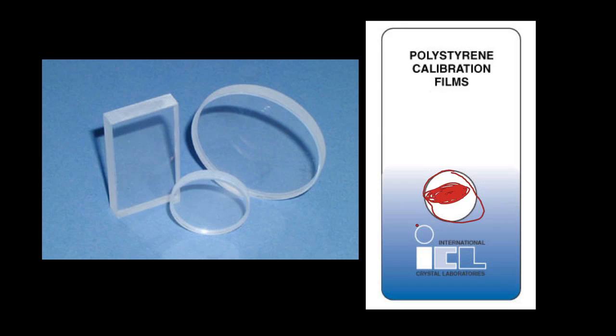Now if you do use a polystyrene film we do have one little problem. Polystyrene is an organic compound, it has covalent bonds in it, and you might be tricked into thinking that what you're seeing on an IR spectrum is coming from your sample when actually it's coming from the polystyrene. So if you use the polystyrene cards what you have to do is run a background spectrum on polystyrene alone. You take the blank card, put it in the cell holder and run an IR spectrum, then you put sample on the card, put it back and run it again, subtract out the background spectrum of pure polystyrene, and what will be left over will be the peaks from your molecule which is suspended on the polystyrene film.